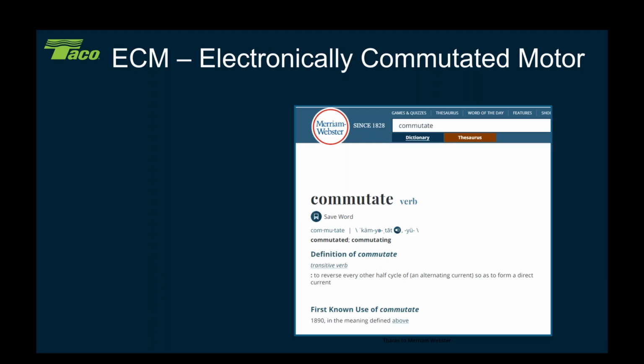ECM motors are permanent magnet, but not all permanent magnet motors are ECM. Okay, that's the big difference. So if we look at the definition, commutated means to reverse every other half cycle of an alternating current. That's what it means. So if we look at that, ECM motors operate with an AC power source, just like a permanent magnet motor does. They both operate with AC power.